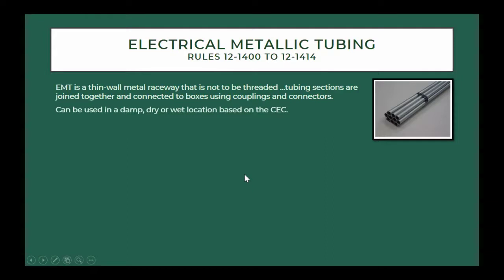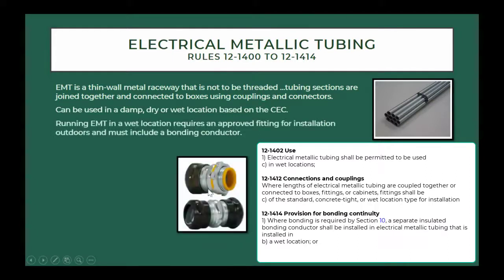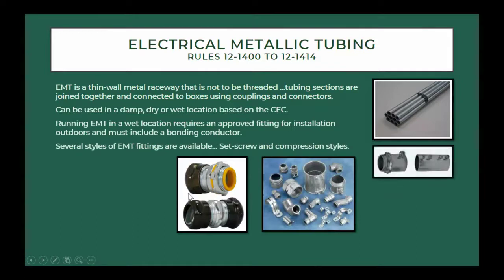It can be used in a damp, dry location. Did you know you can use it in a wet location now? Because everybody was doing it. So they said, because everybody's doing it, let's just say we can use it, provided that they use these rain-tight connectors. So EMT in a wet location requires an approved fitting for installation outdoors and must include a bonding conductor.